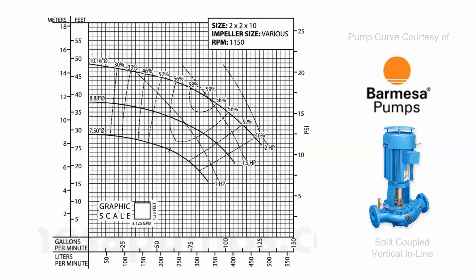This pump curve also shows efficiency, but in a somewhat different format. The efficiency is laid out by tick marks — 30, 39, 46, 52 — representing the percentage of efficiency at that particular spot on the performance curve, and these form curves themselves. The most efficient this pump can be is 59%, and the center line of that efficiency runs from the most efficient point for each particular impeller trim, which corresponds relatively to the center of that performance curve.